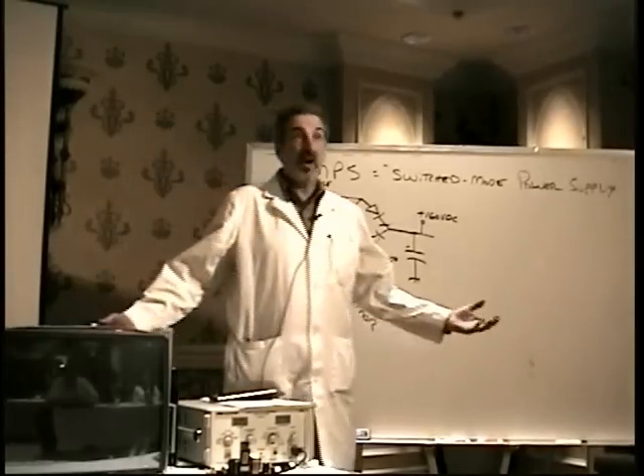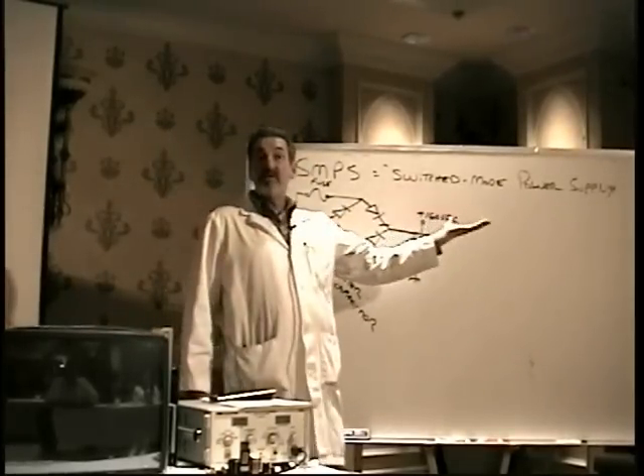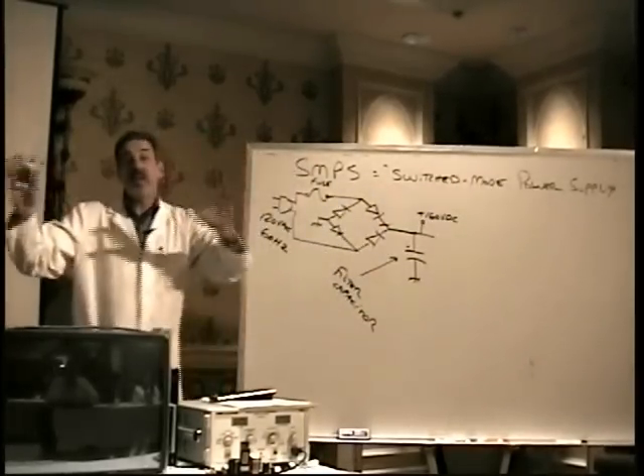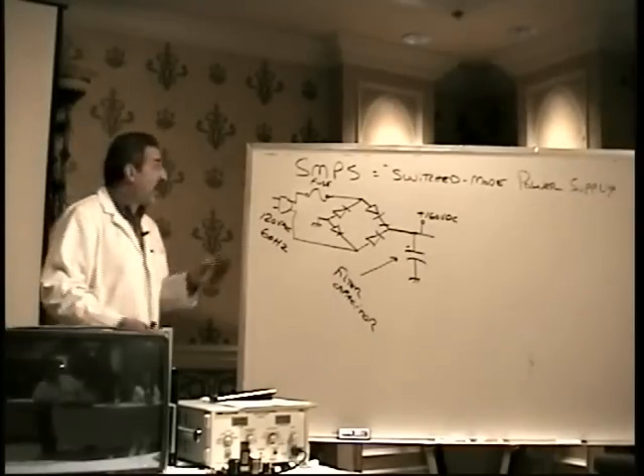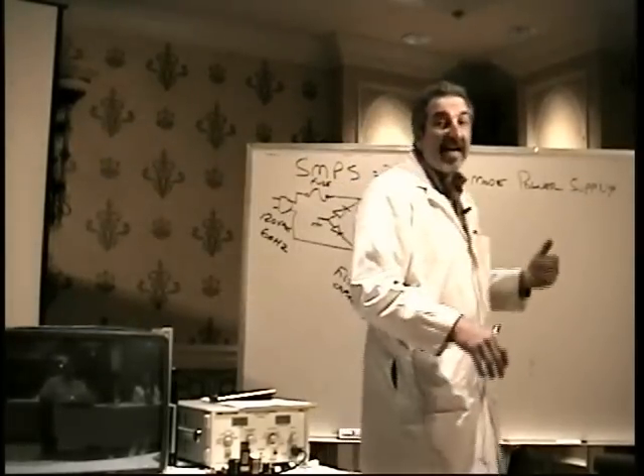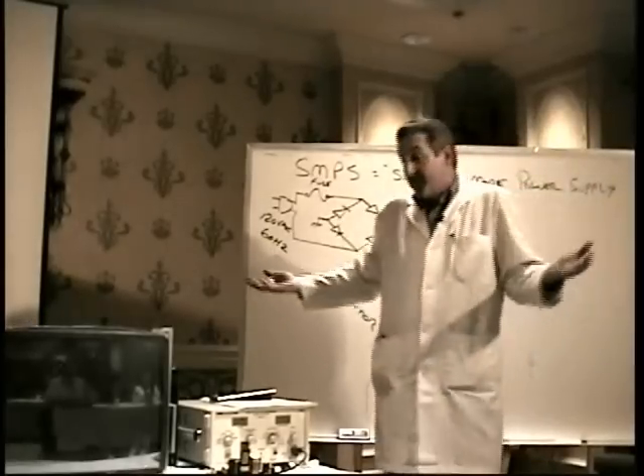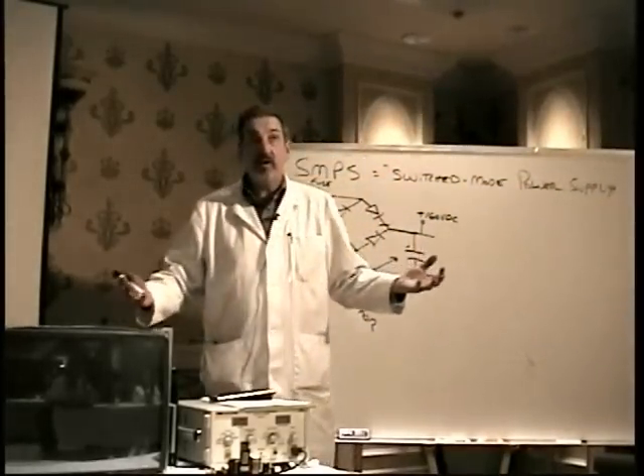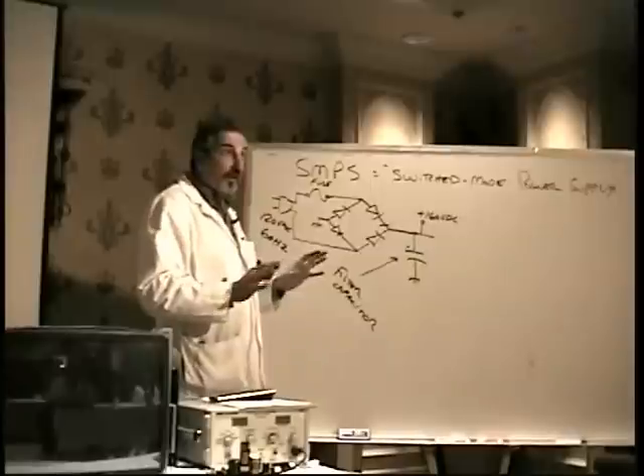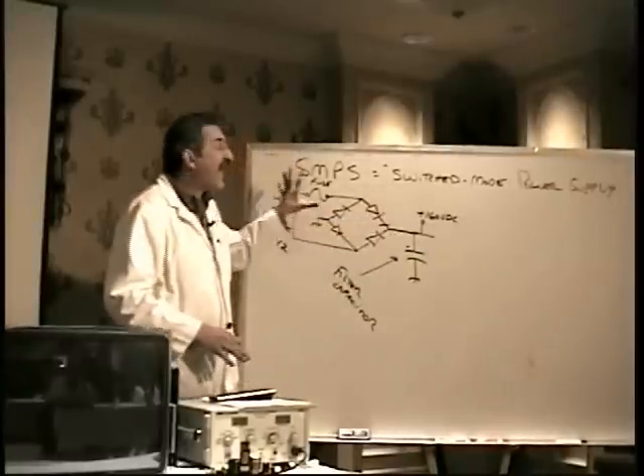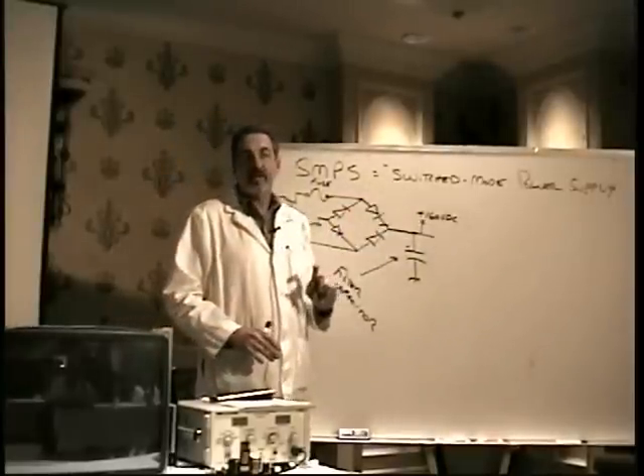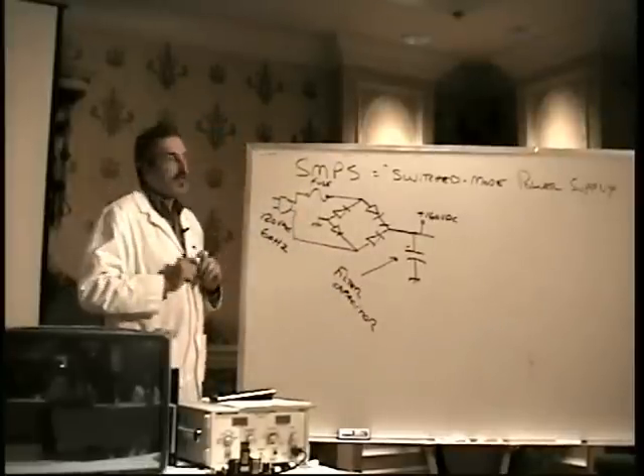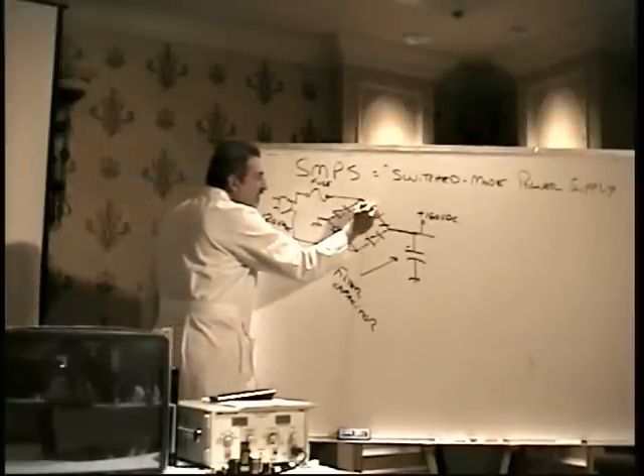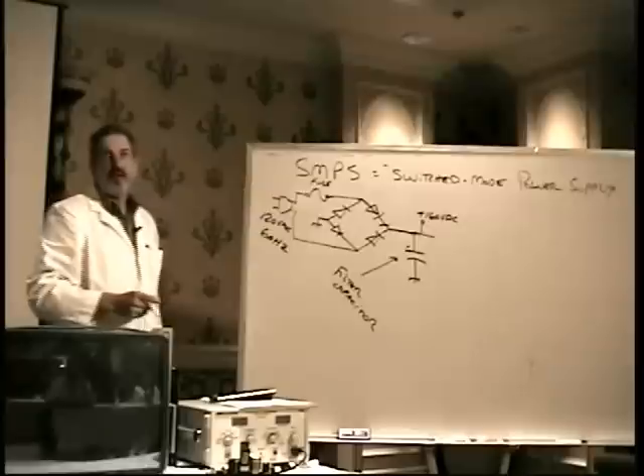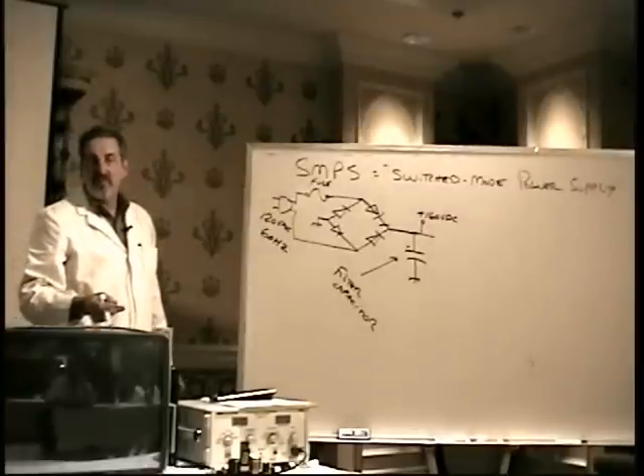Where did we get the extra voltage? We put in 120 — how did we end up with 160? Pretty weird, but that's perfectly normal. Anytime we turn AC into DC, the DC we get out ends up higher than the AC we put in to begin with. That's perfectly normal, and nothing could fail here to cause that voltage to be too high. The only thing that could fail at this point is a diode or two in the bridge rectifier. When diodes fail, they typically short circuit — 999 times out of 1,000, maybe even more often than that.